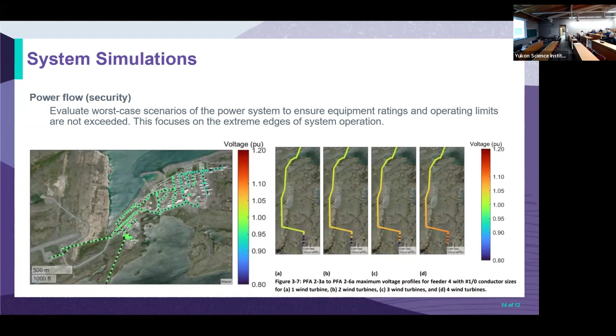The issue is that having multiple different generating sources can have impacts on the voltages around the community, because we have such low voltage and no transmission grid. You can see that if you add more wind turbines at the end, you get impacts on the voltage. One wind turbine is pretty good, but four wind turbines gives really high voltage, and that's typically not good for the equipment and the transformers.